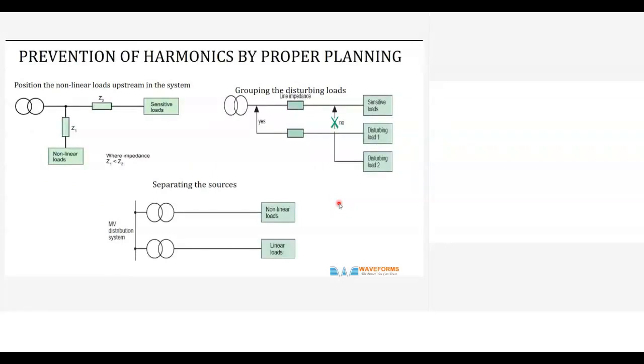You can keep the sensitive loads away from the harmonic-producing loads, called non-linear loads. Or you can group them separately, the disturbing loads and the sensitive loads, because disturbing loads closer to sensitive loads would be a real problem. So keeping them away from the sensitive loads is very important. Then separate the sources with different transformers, so that even filtering a non-linear node becomes simpler. Once you mitigate harmonics closer to the non-linear node, it will not affect the power factor and all that. So this little planning can be done when designing it. There are also other techniques of mitigating harmonics.